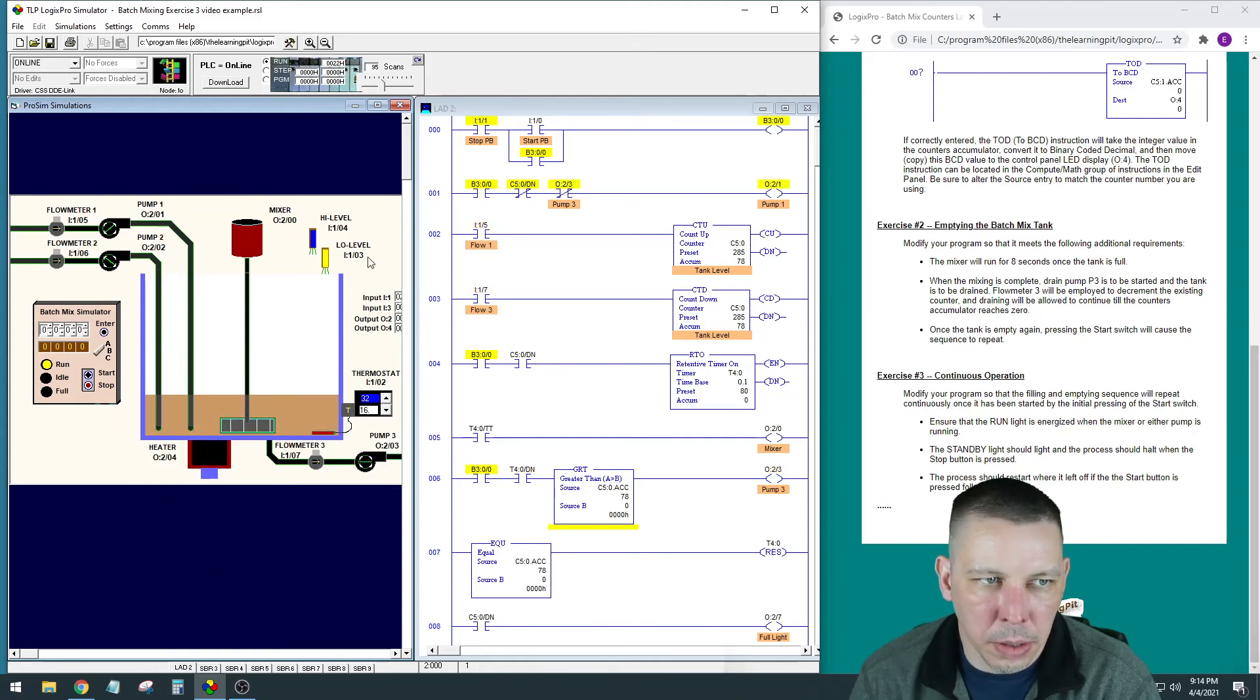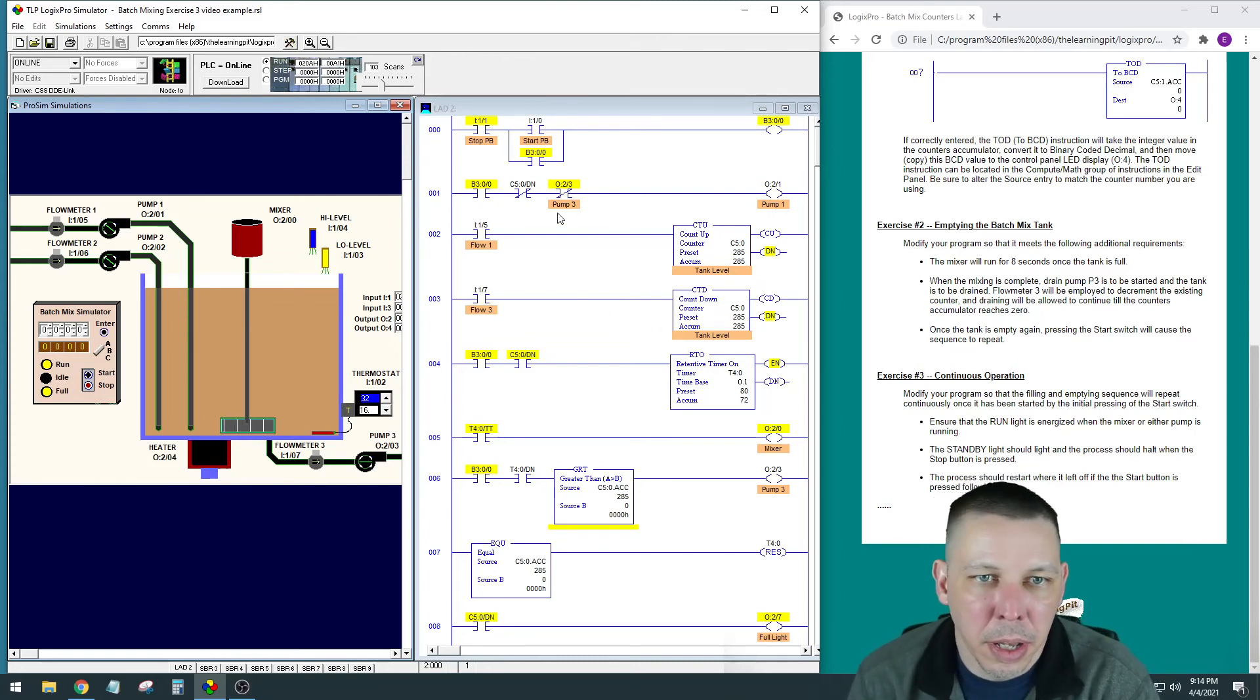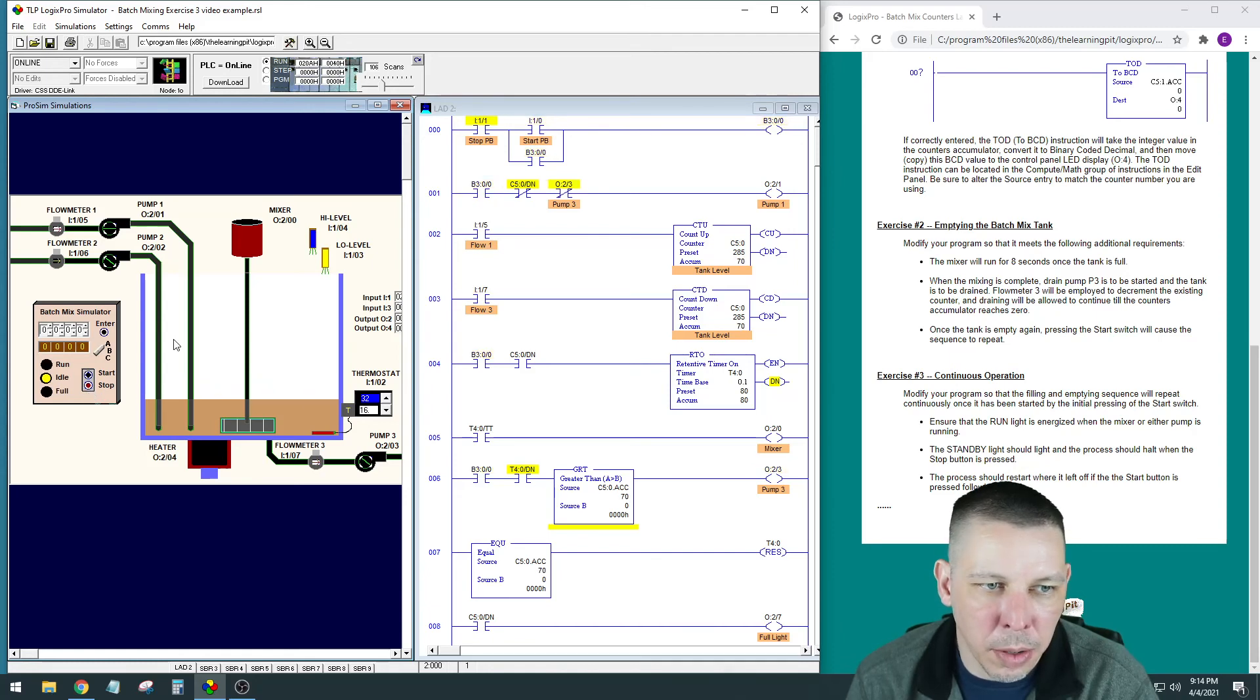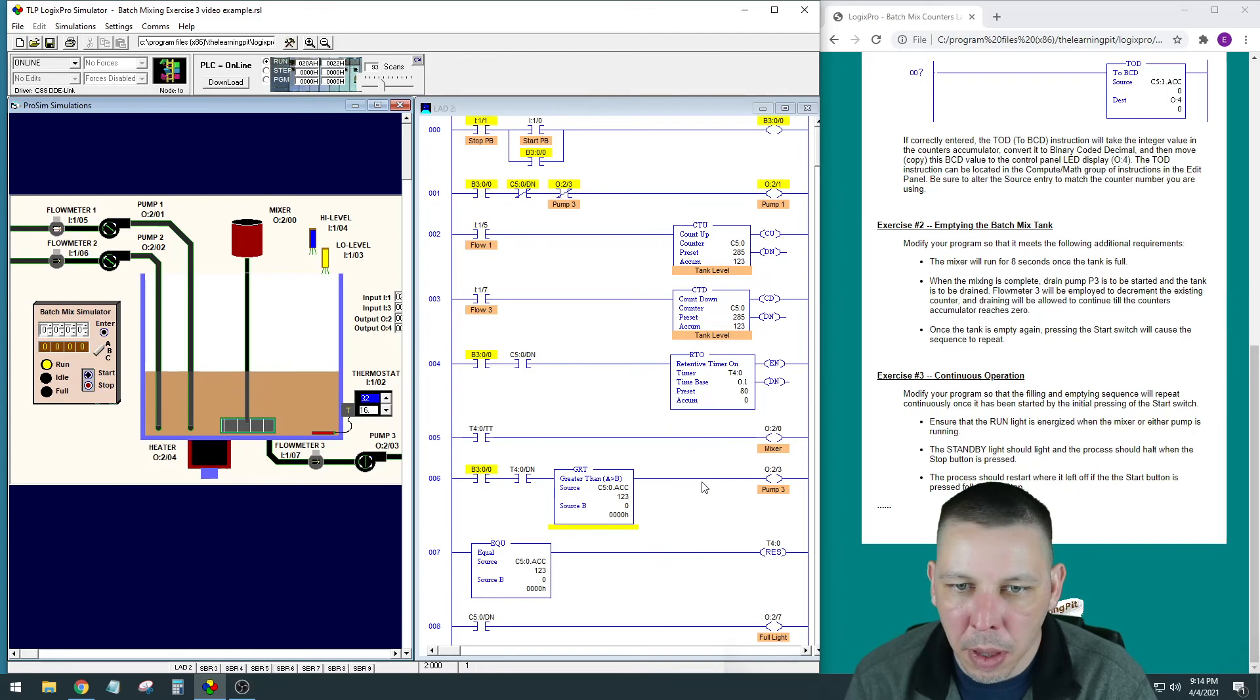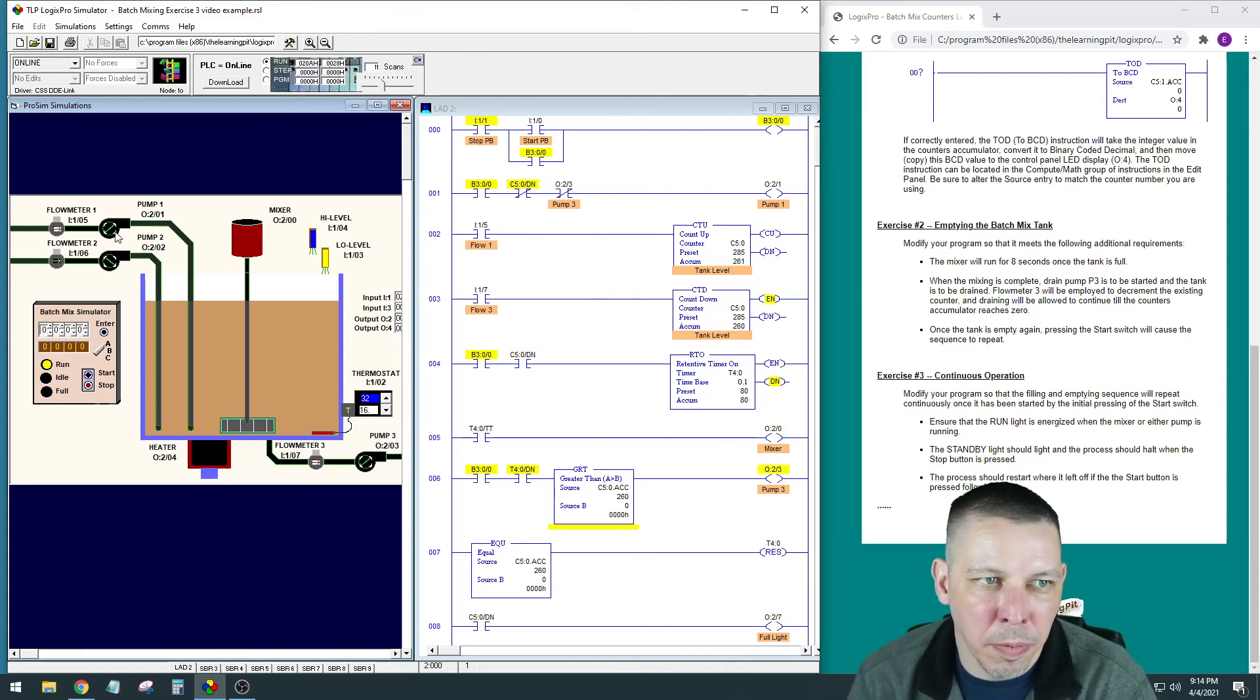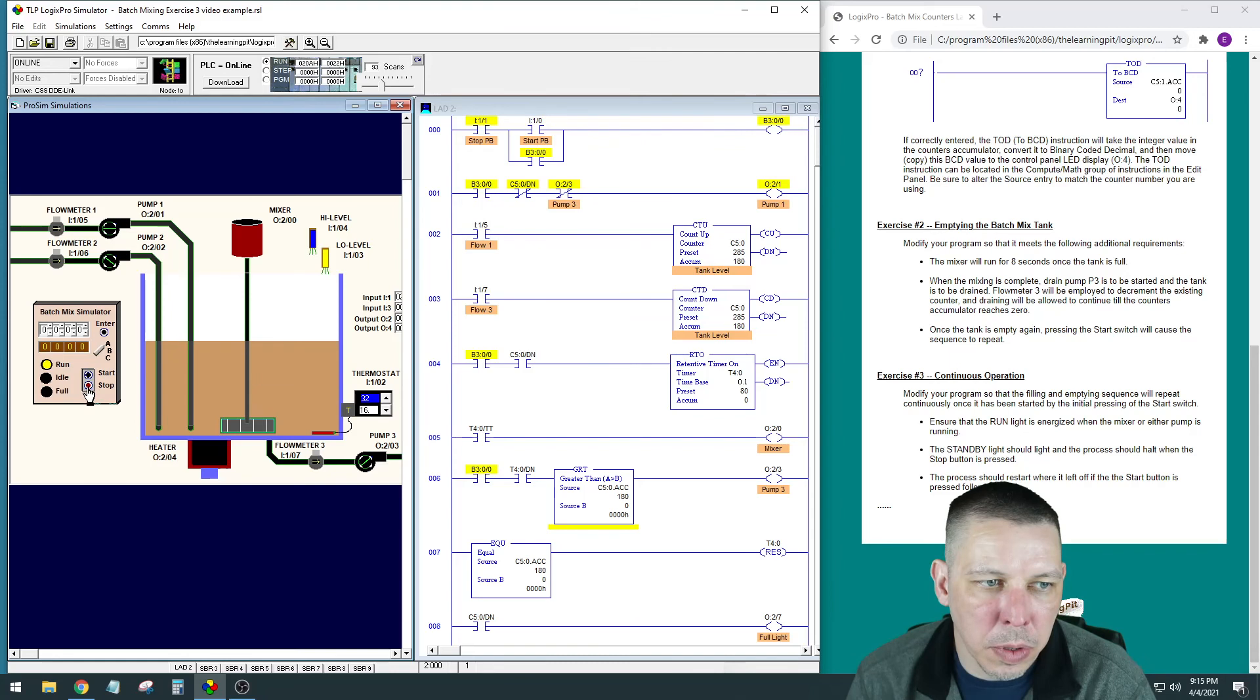And it's cycling. It's cycling because it's still enabled with this bit up here—everything that needs to actually run. And then everything else is just based off the things that are running, like the count ups and countdowns are based off flow meters that get their pulses based on when the pumps are running. Before, I'd stop it and hit start again and it wouldn't continue down—it would fill back up again. That was because my timer was zeroed out. So I had to adjust it so that my timer would only be zeroed out after it was done pumping all the way down. In this case, that is when the accumulator gets back down to zero. And the only time that the accumulated equals zero is right then, because as soon as pump one starts coming on, the first flow meter increment makes it not equal zero anymore. So it's really the only time in the sequence that that happens.